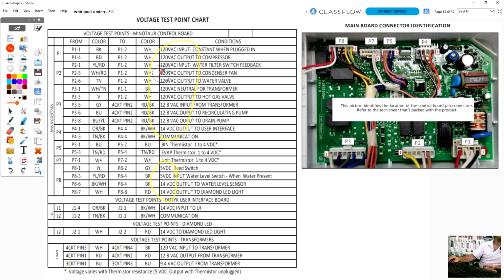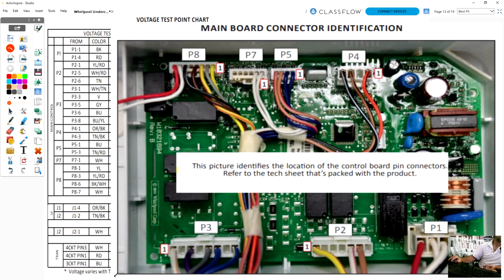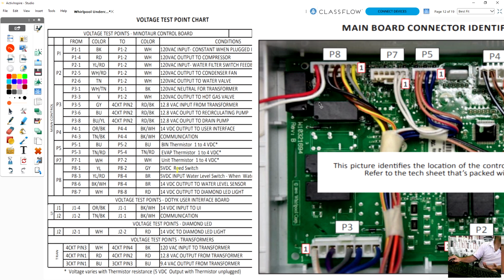How you use this to test the components is the P's and J's are the actual whole connector that the wires are connected to the board with. The -1 or -4 is, if we look at this connector, and let me zoom in on it just a little bit, just so people know when they're testing from the board what that means and how to test from the board. Let me pick a component out. Let's go to neutral transformer, 120 hot gas valve. This neutral for the transformer can be used for the transformer as well as the hot gas valve. They're both 120 volts. So I could use plug 3 pin 1, plug 3 pin 3.